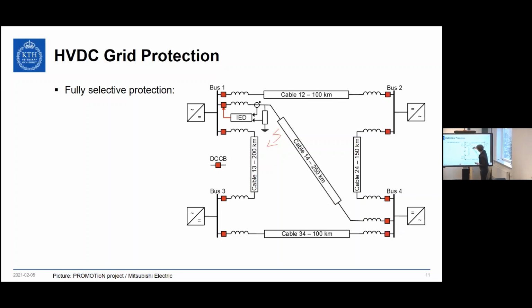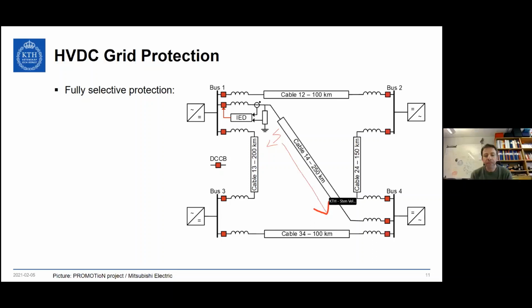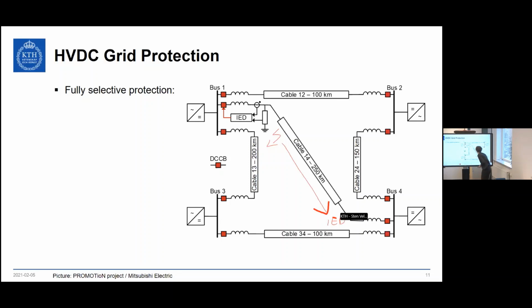Now, if you were to use double-ended fault detection for this kind of fault, the traveling wave has to go here, at say 200 kilometers per millisecond — that takes about a millisecond. Then you have an IED here that has to detect a forward fault, taking maybe another half millisecond, and then you have to send a communication signal back, another millisecond. So we're at about 2.5 milliseconds extra compared to only detecting single-ended.